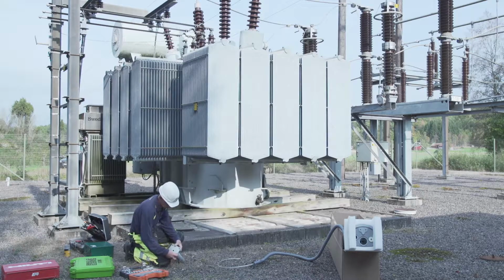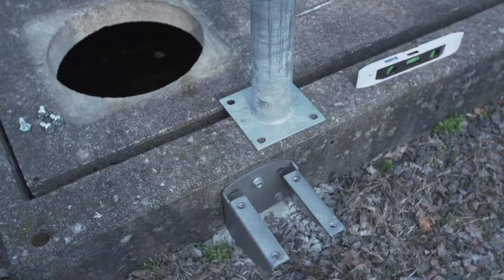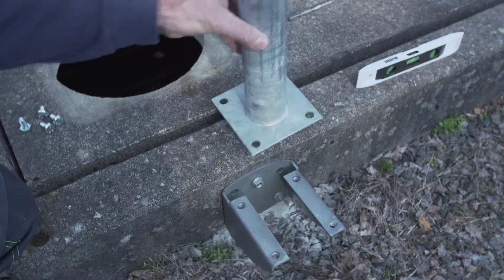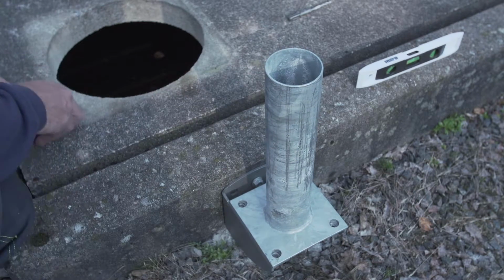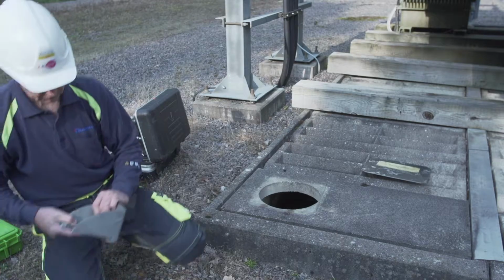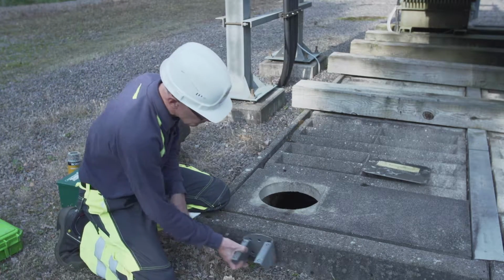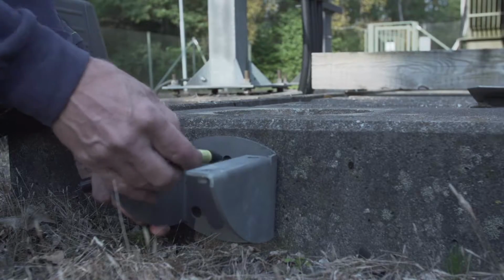Unscrew the wall bracket and remove the installation pole from the unit. Determine whether it is best to mount the unit standing on the rim or sitting on the wall or plinth using the wall mounting plate. Hold the wall bracket at the selected installation height or place the installation pole directly onto the rim.